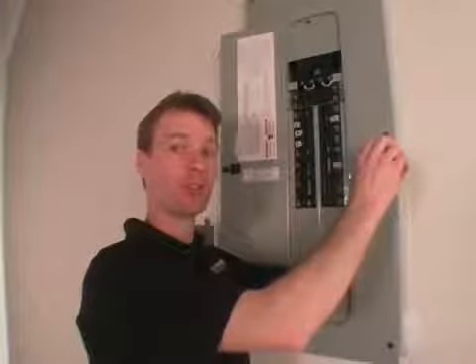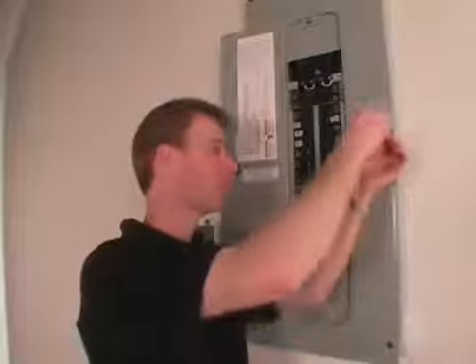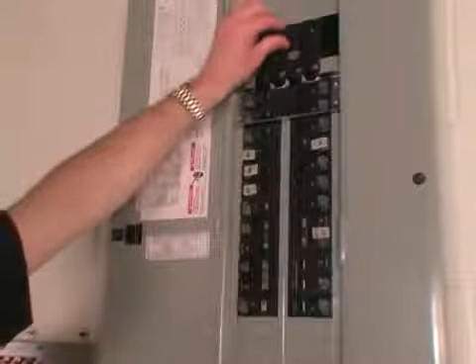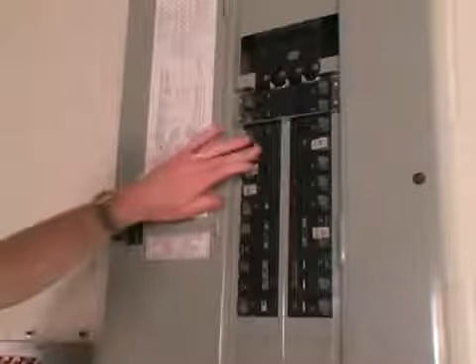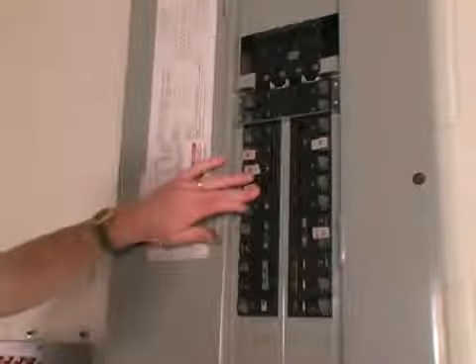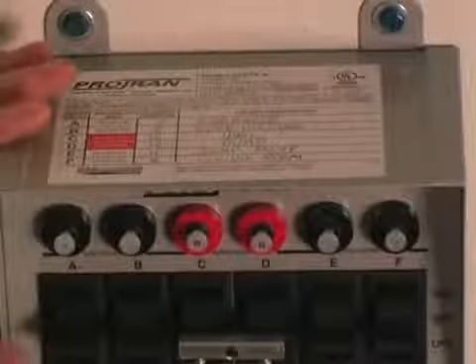The only thing left is to put the cover back on the panel and turn the circuit breakers back on. It's always a good idea to double check your wiring before you attach the cover. With the cover back on, we can turn the main breaker back on and the individual circuits we turned off during installation. There is a label on the top of the transfer switch that allows us to make a record of what the switches control.